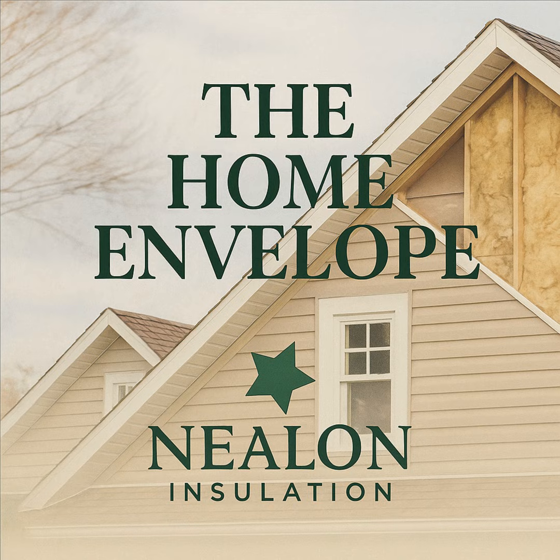Baffles. Yeah, a baffle is a rigid chute, usually plastic or foam, that gets stapled to the underside of the roof deck right where the roof meets the wall. Okay, so it blocks the insulation. Exactly. It acts as a protective tunnel, holding back the insulation while guaranteeing a clear, unobstructed channel for the fresh air to enter the attic.